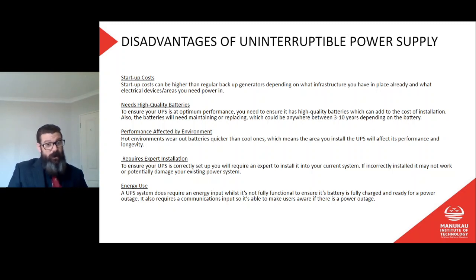We need very high quality batteries. To ensure your UPS is at optimum performance, you need high quality batteries, which can add to the installation cost. The batteries will need maintaining or replacing, which could be anywhere between 3 and 10 years depending on the battery. They won't last forever, even if you don't use them, even if they just sit there on charge for a couple of years — they are going to wear out.